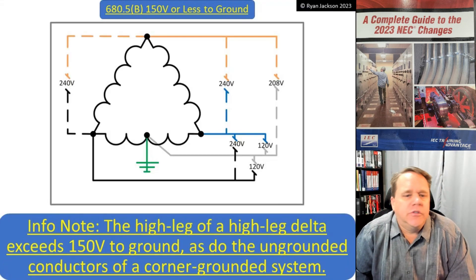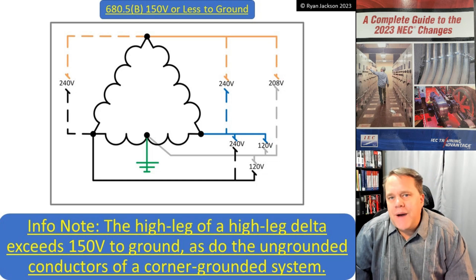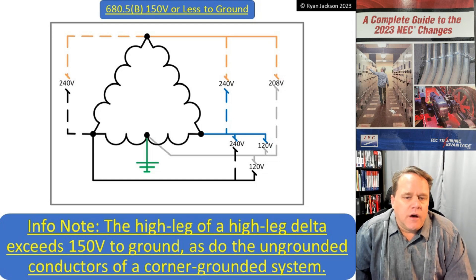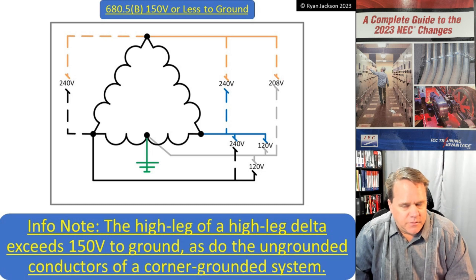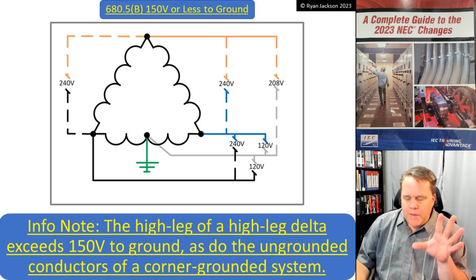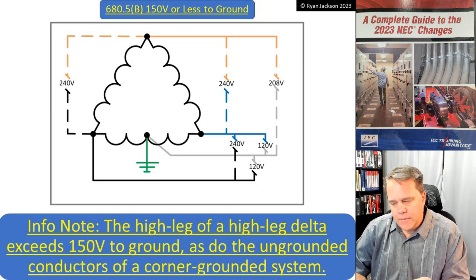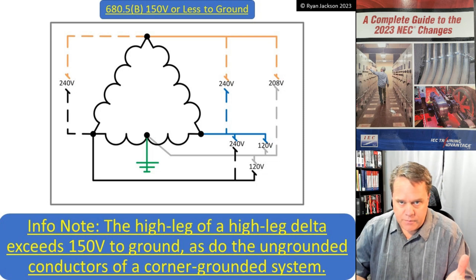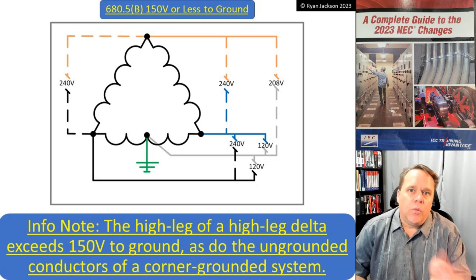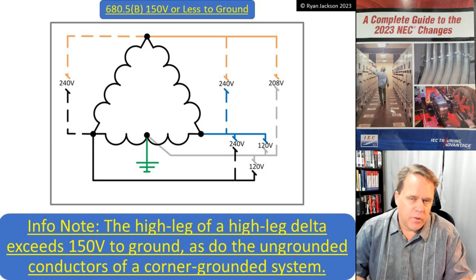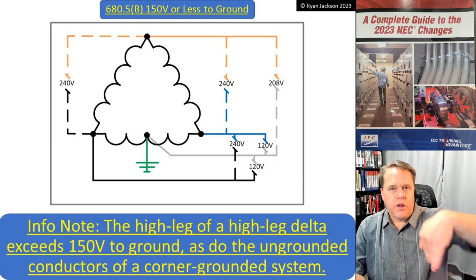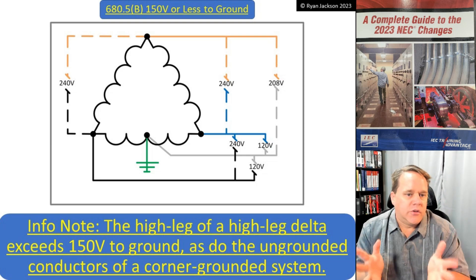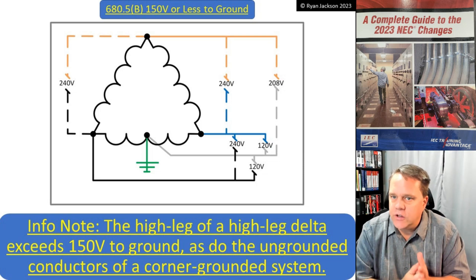There's an informational note that reminds us the high leg of a high-leg delta exceeds 150 volts to ground, as do the ungrounded conductors of a corner-grounded system. So maybe I have a three-phase swimming pool pump that requires GFCI protection. If it's on a 120/208-volt three-phase circuit, then 120, 120, 120 — all of those are less than 150 volts to ground — so you would need Class A GFCI.